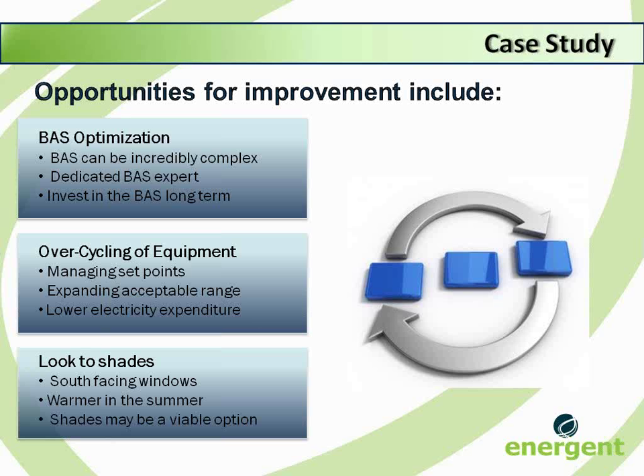Finally, many hospitals have increased the amount of windows installed in the building to encourage natural light within the hospital. In warm summer months, this can cause a significant increase in cooling requirements because the natural light warms the area, but in shaded areas, the temperature sensor might read a significantly lower temperature, so the BAS becomes confused.